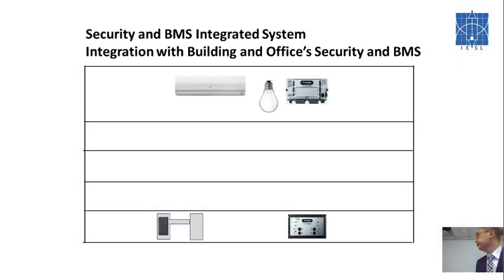Here's another example. Let's say it's an office building where the landlord has his own security system and the tenant has his own BMS system—we can integrate these. When I come in to work, I tap my card on the turnstile, which talks to the DDC controllers and the card access controllers, and the flaps open. At the same time, the card access controllers talk to the DDC via BACnet. So on my way to the lift, the lighting and aircon switch on based on my desired set point. When I reach my office, everything is ready for me to work. As I leave the building, I tap on the landlord's turnstile, which communicates with the card access controllers and DDC controllers, and everything switches off. So we're integrating the landlord's card access system with my office's BMS system—this is integration to save energy.